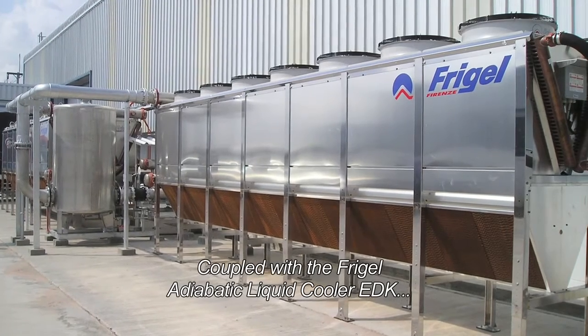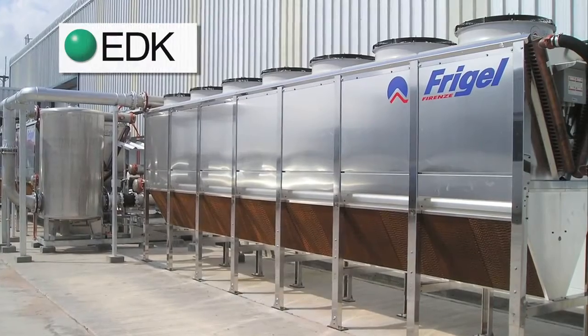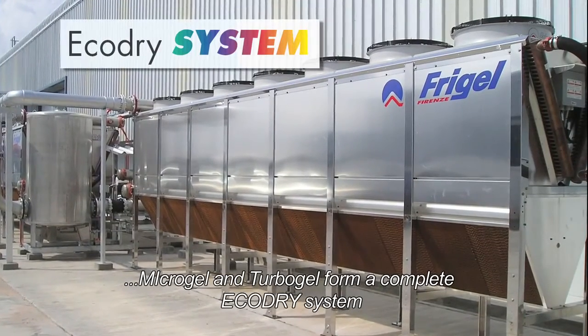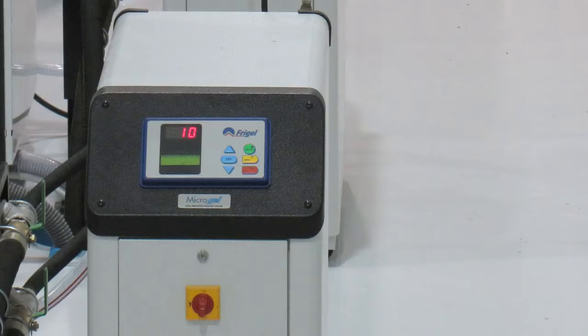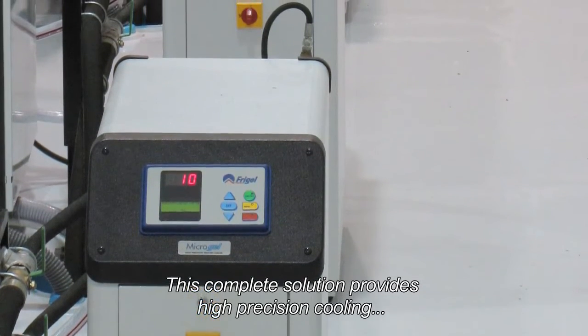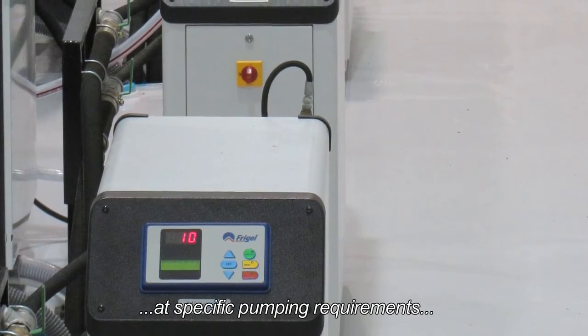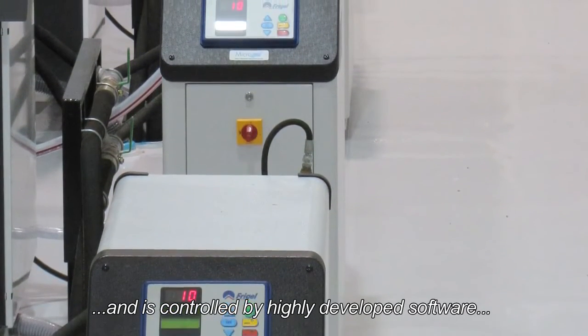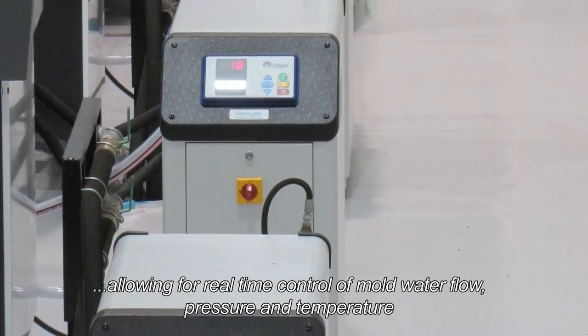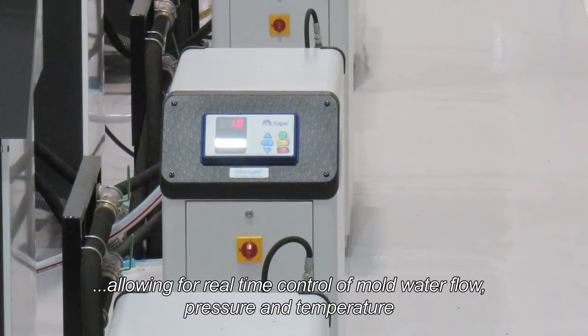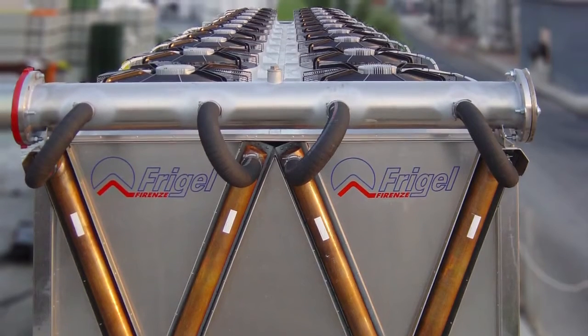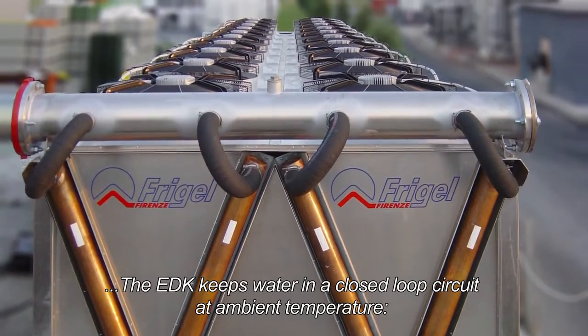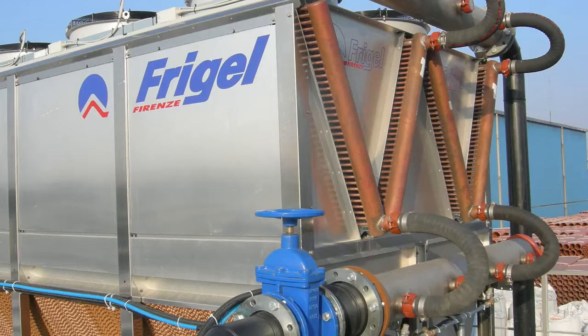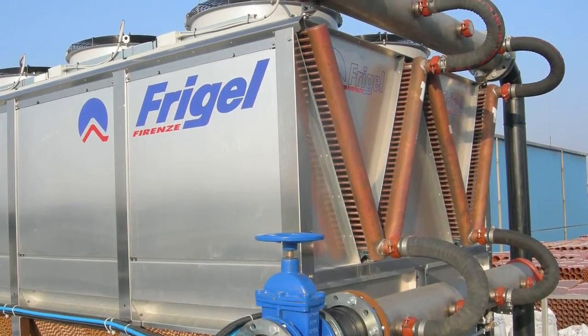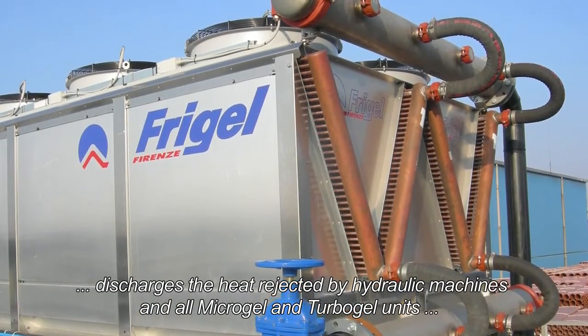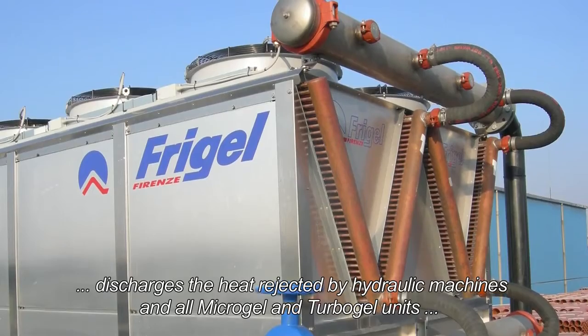Coupled with the Frigel adiabatic liquid cooler EDK, microgel and turbogel form a complete Ecodry system. This complete solution provides high-precision cooling at specific pumping requirements and is controlled by highly developed software, allowing for real-time control of mold water flow, pressure, and temperature. The EDK keeps water in a closed-loop circuit at ambient temperature. This water, without any evaporation, discharges the heat rejected by hydraulic machines and all microgel and turbogel units.